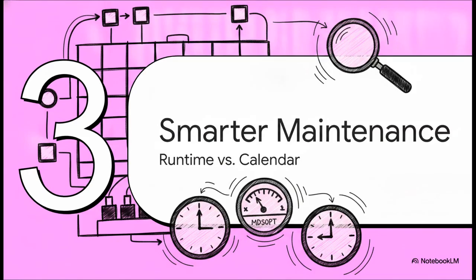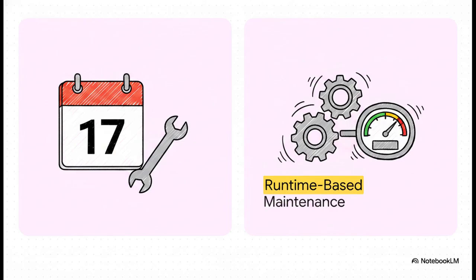Section 3. Smarter Maintenance, Runtime versus Calendar. Okay, let's take a step back and look at the bigger picture to see how we apply this continuous monitoring mindset to the broader power system using the MDS-OPT function. For decades, the industry has relied on calendar-based maintenance. You service a machine every 6 months, regardless of how much it was actually used. It's exactly like relying on a fixed date on a sticker in your car window for an oil change, rather than checking your actual odometer. By utilizing actual runtime data instead, we prevent wasted maintenance on equipment that just sat idle, and we prevent unplanned failures on equipment that's been working overtime.